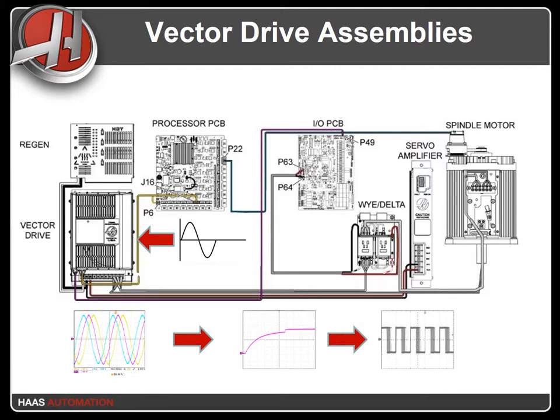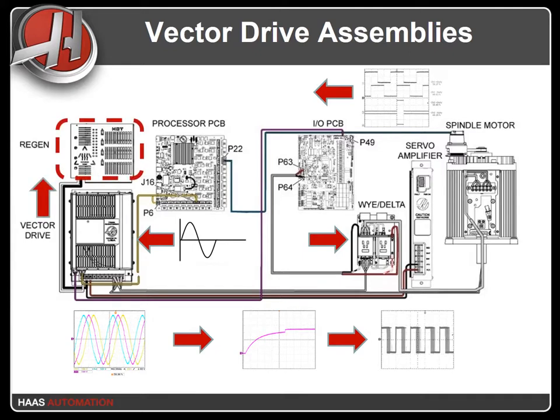As the spindle motor spins, its encoder generates feedback signals that represent its velocity and position. When the spindle motor reaches a certain velocity, the controller sends a command to the IOPCB to cycle the Y-Delta contactor assembly to switch from Y to Delta, and from Delta to Y during deceleration. When the motor is commanded to decelerate or stop, the motor generates back voltage. This voltage goes back to the drive's DC bus. The drive constantly monitors the DC bus, and when the voltage reaches a certain level, the drive dissipates the extra voltage through the regen load.